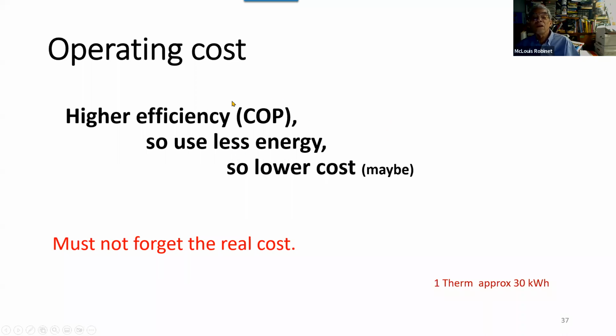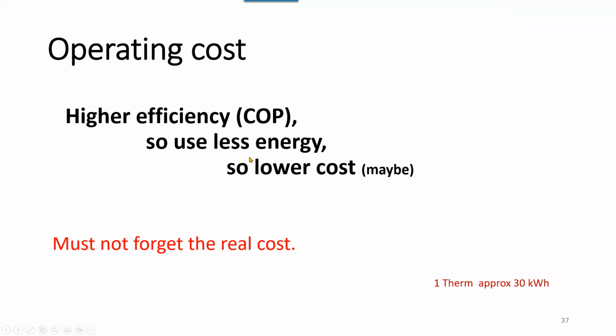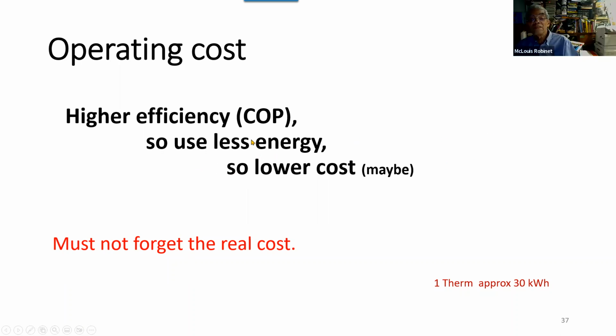So even though the cost is double, it's a wash because we're using half the amount of energy. If, say, the cost of electricity was 3 times more, and we got a heat pump with a coefficient of performance of 3, it's still a wash. But if we're using a heat pump with a coefficient of 2 and electricity 3 times more, then it's costing us more than it would if we used gas.